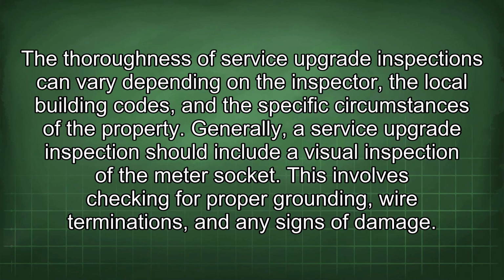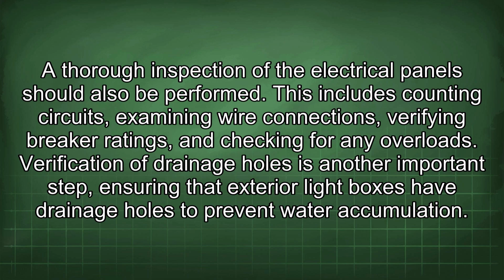The thoroughness of service upgrade inspections can vary depending on the inspector, the local building codes, and the specific circumstances of the property. Generally, a service upgrade inspection should include a visual inspection of the meter socket. This involves checking for proper grounding, wire terminations, and any signs of damage. A thorough inspection of the electrical panel should also be performed. This includes counting circuits, examining wire connections, verifying breaker ratings, and checking for any overloads.